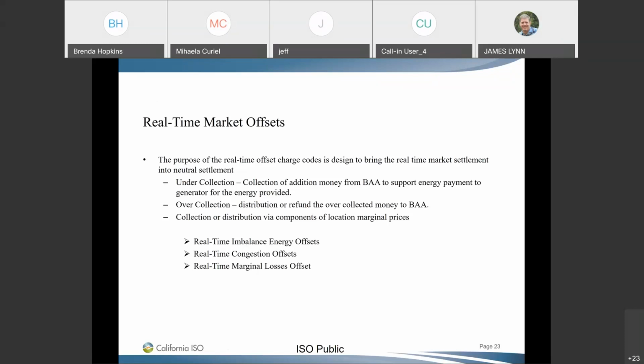Interties, if they are updated based upon their pre-hour schedules, you're going to see dispatches or awards in the 15-minute market for interties and generation, and then generation mainly for the RTD. Now, there's a settling at 5-minute LMP. When we get the meter value, generation should still be at a 5-minute. Interties can either be 15-minute or hourly values that have been distributed across the 12 intervals of that hour.